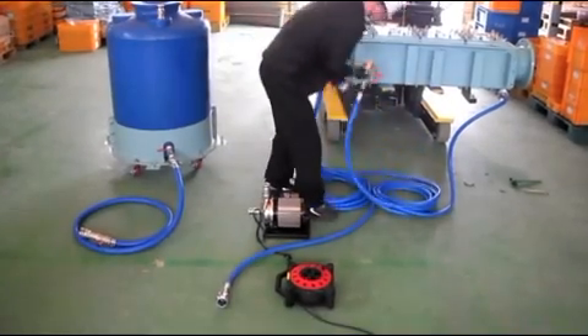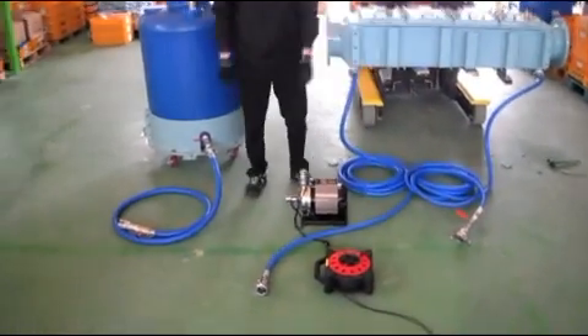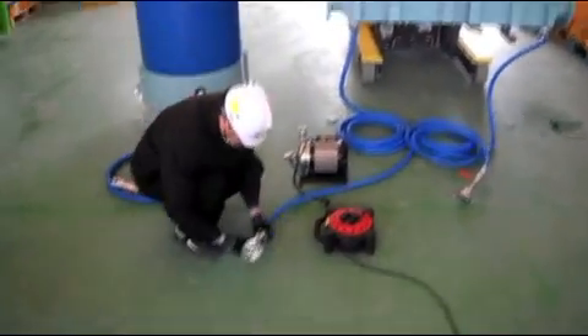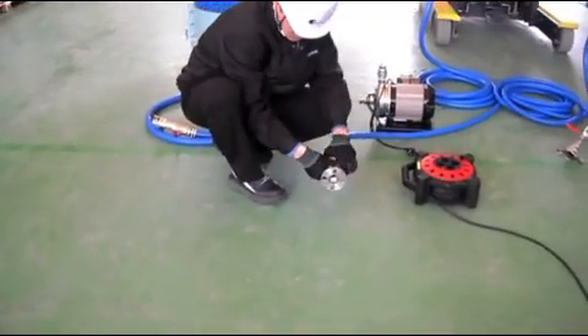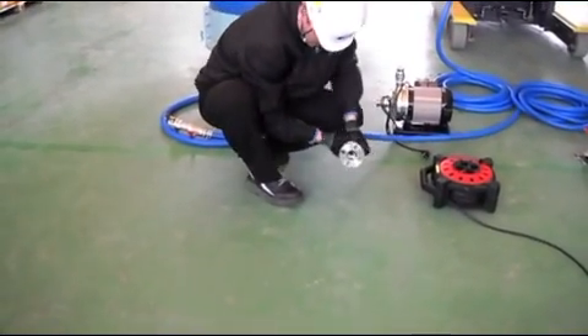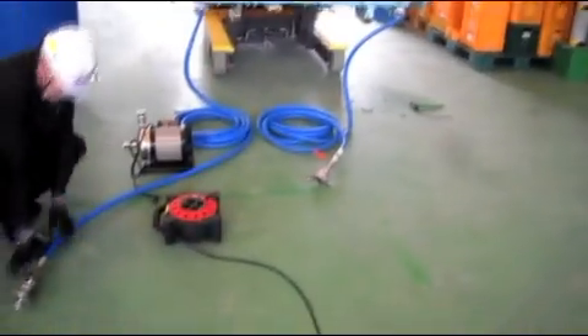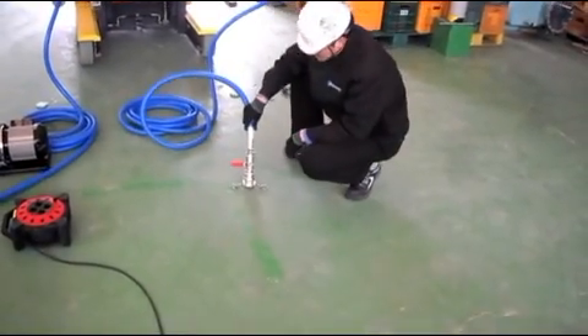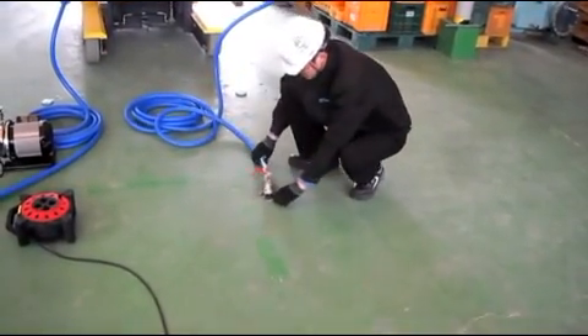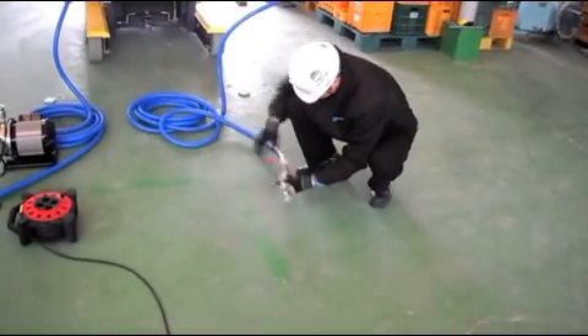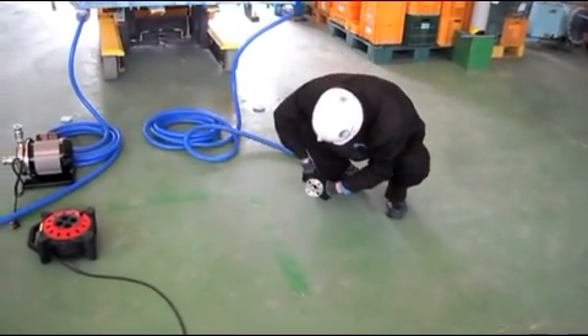3. Drain seawater from chamber through drain D1, D2 of ECU. 4. Inject cleaning agent with fresh water. Please refer to Table 1 below for the appropriate amount of cleaning agent and fresh water. 5. Disconnect the fresh water pipe from tank T2.